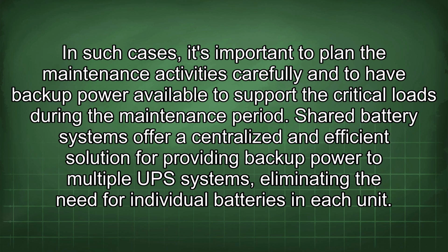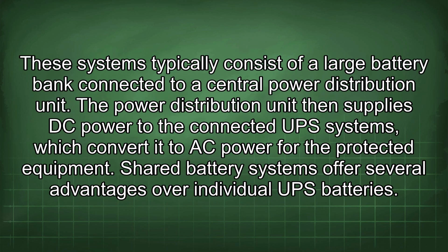Shared battery systems offer a centralized and efficient solution for providing backup power to multiple UPS systems, eliminating the need for individual batteries in each unit. These systems typically consist of a large battery bank connected to a central power distribution unit. The power distribution unit then supplies DC power to the connected UPS systems, which convert it to AC power for the protected equipment. Shared battery systems offer several advantages over individual UPS batteries.